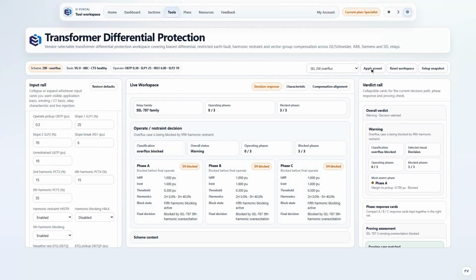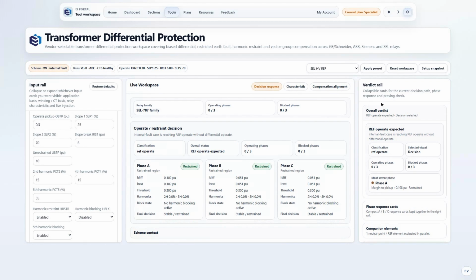Finally, let's look at an earth fault near the star point. The phase differential barely registers, 0.1 against a pickup of 0.3, so it does not operate, and on its own it would miss the fault entirely. But the 787 sequence directional restricted earth fault element is watching the neutral CT. Operate current 0.8 against a threshold of 0.1, and it trips. The restricted earth fault catches exactly what the phase element misses. That companion element is why you fit it.